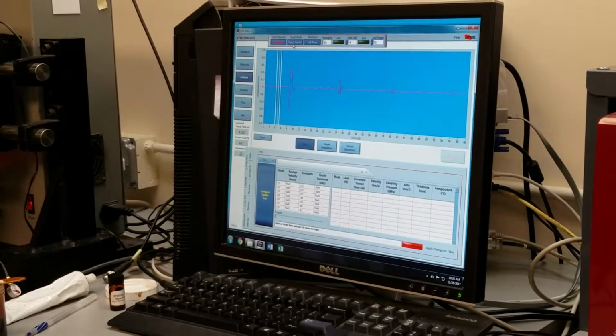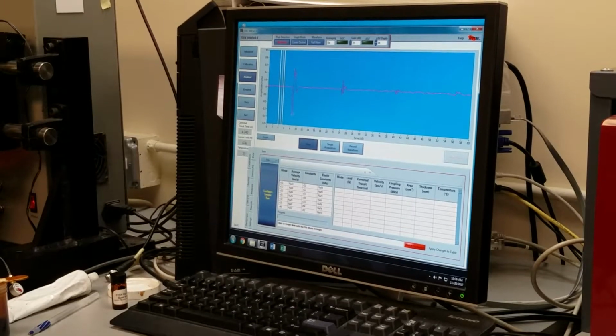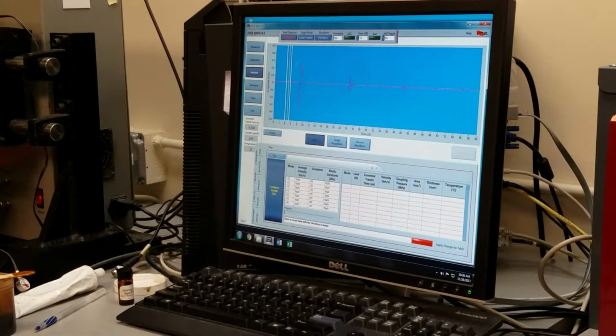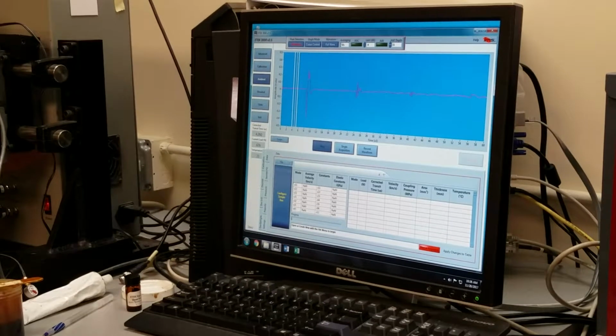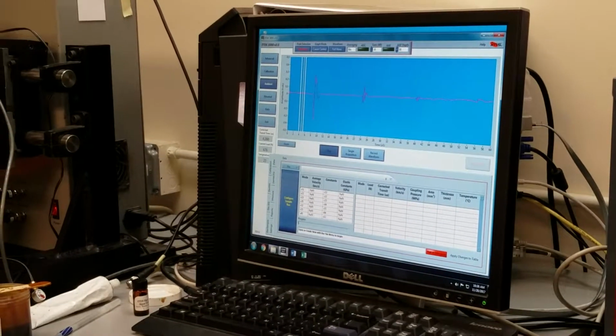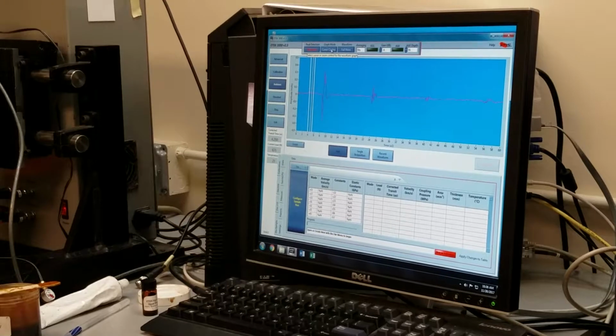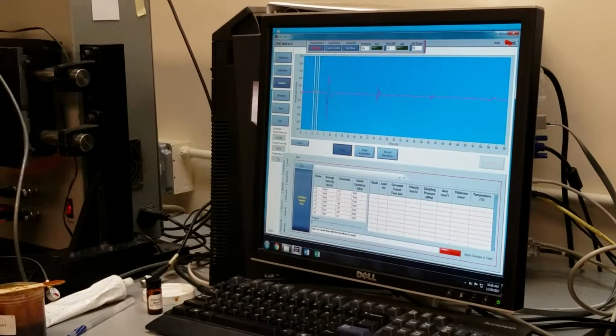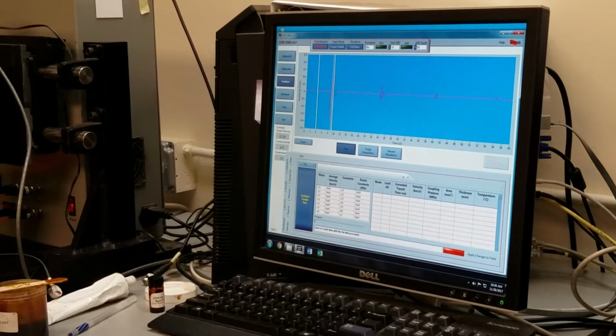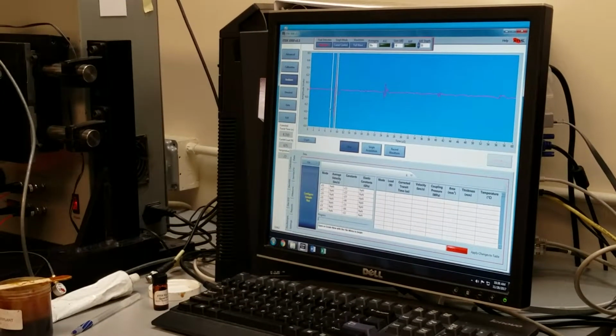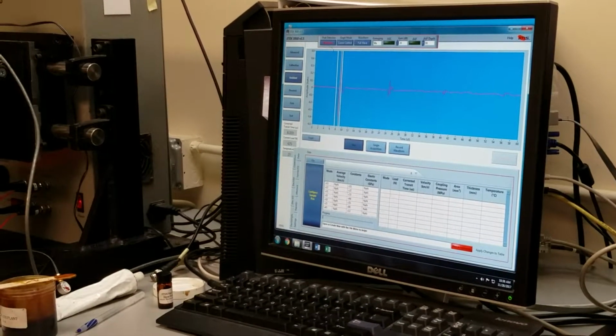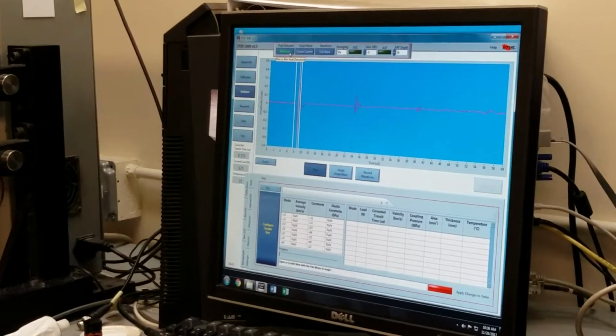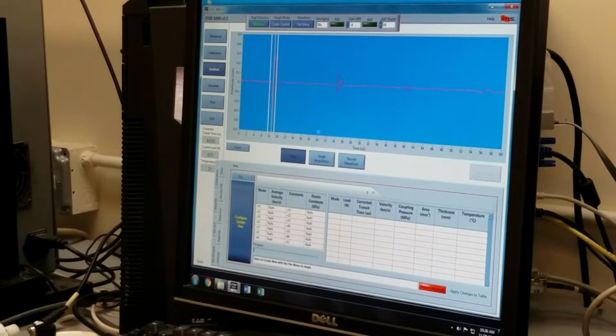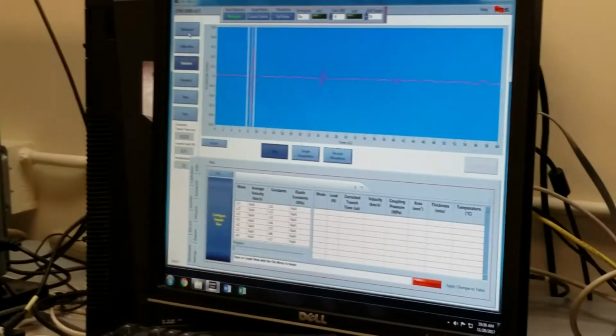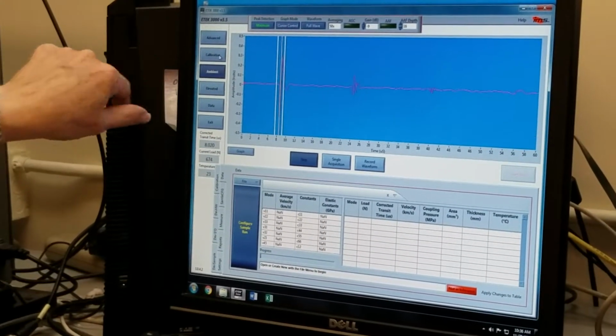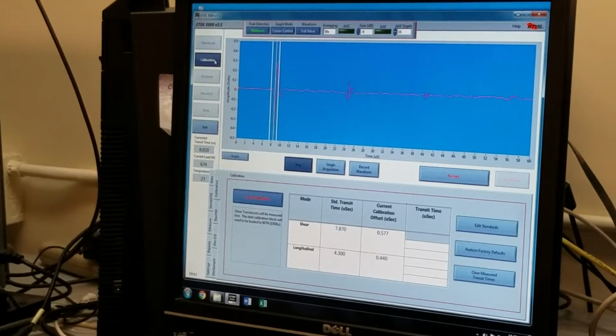The next thing that I want to do is measure where this trough is. So I want to move my measurement cursor, which is the yellow vertical line. I'll double click on cursor control and drag the white vertical lines so that they are on either side of this trough. For the peak detection, I want that to say minimum, and since I am doing a calibration, I'm going back over to the left-hand side of the screen, and I'm going to select calibration.